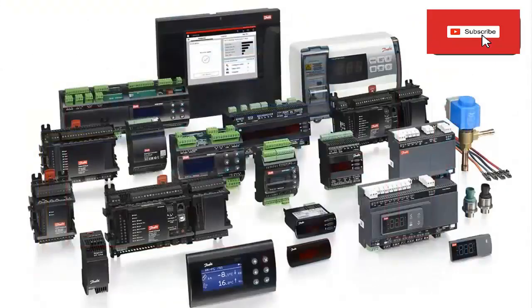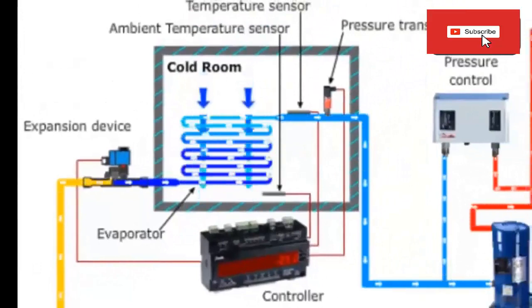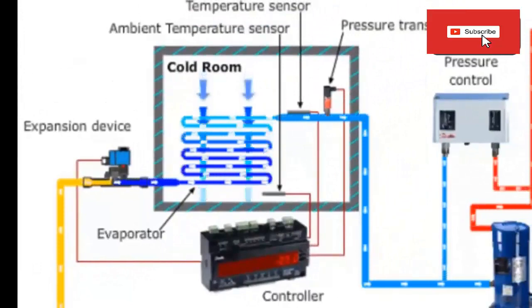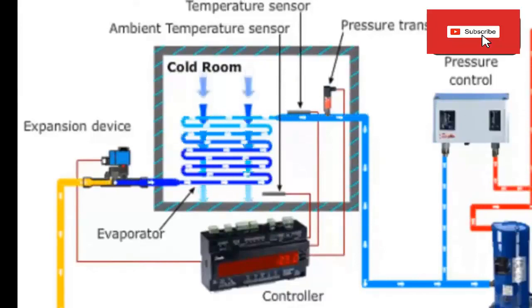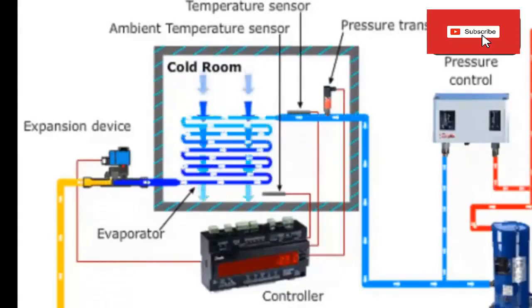The electronic room controller is responsible for managing the electronic expansion valve according to the pressure and temperature values shown by the sensors. This precise control allows exact control of the superheat at the outlet of the evaporator. In this way, energy consumption can be saved and the compressor can be protected at the same time.